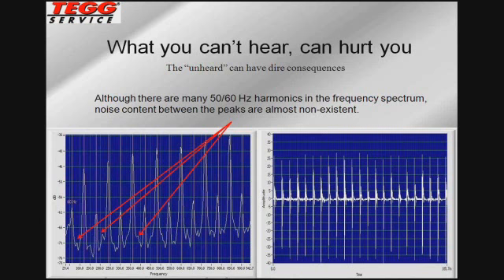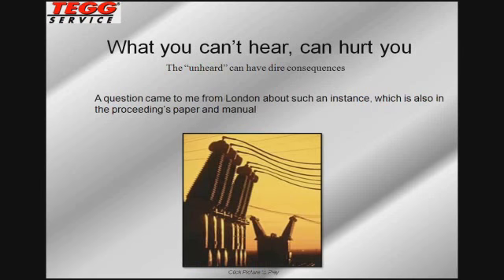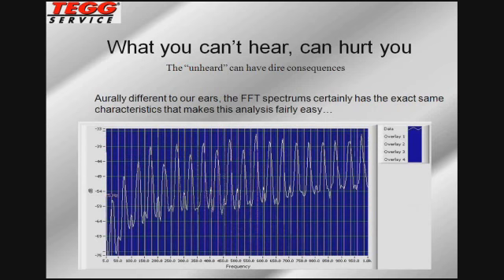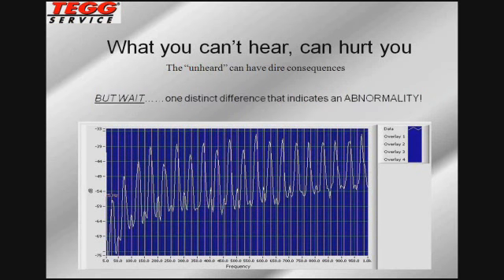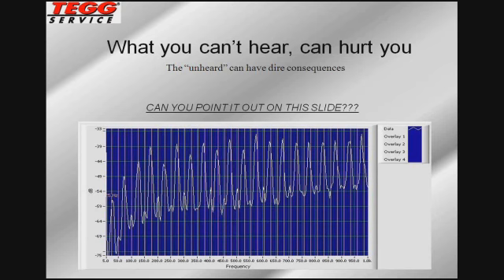Now, when you have problems within transformers, there are certain things you can look out for. You don't want to confuse corona with the vibration I just showed you. Remember that corona is rich with frequency content, whereas if it is 50 or 60 cycle hum or any type of vibration, that noise content will be absent. I had a technician from London send me a recording that produced this spectrum. It sounded very different than some of the things we had heard, but the spectrum looks similar to what I showed you on a properly functioning transformer. But there was one distinct difference on this particular transformer that I wanted to call attention to. In the proceedings, I said, can you point this out to me? The reality is the additional component exists with a 25 hertz fault frequency.